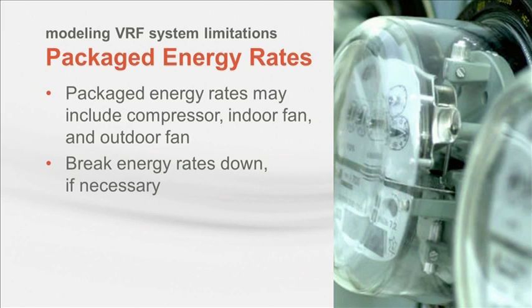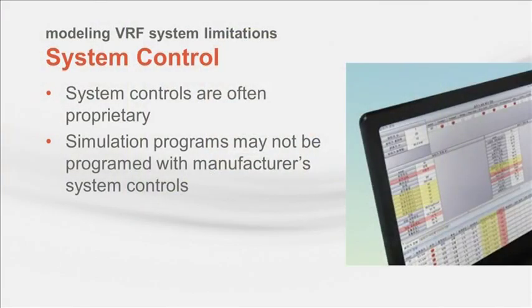Some simulation programs have the ability to automatically break the energy rates out based upon user-specified indoor and outdoor fan power. Check with your software vendor to see which components are simulated and how. From there, you should be able to determine which component energies should be entered into the simulation. Finally, each VRF manufacturer creates their own proprietary system control algorithms. VRF systems may operate differently from one manufacturer to another. This means that simulation programs are not able to exactly replicate how the entire system is controlled. The individual zone control may be difficult to mimic in the simulation since it's hard to predict what each occupant is going to do with their own remote control.